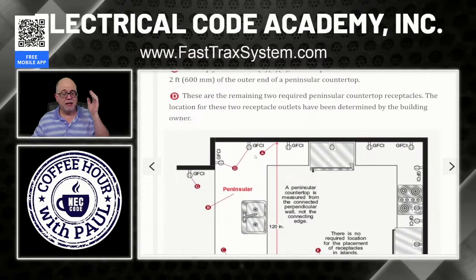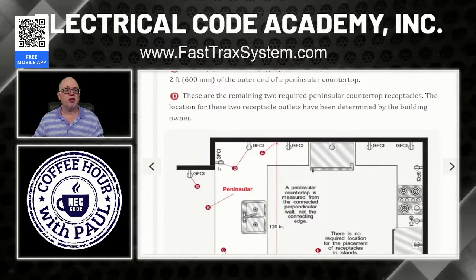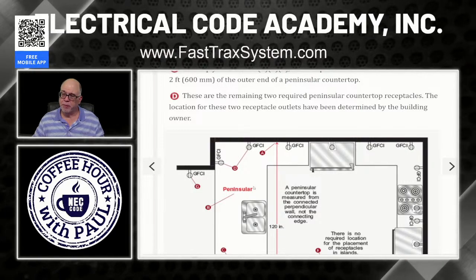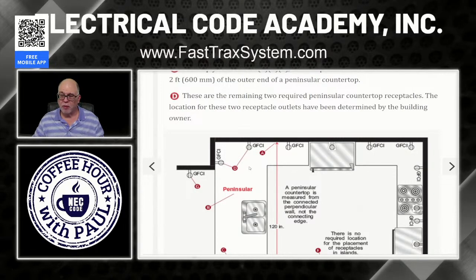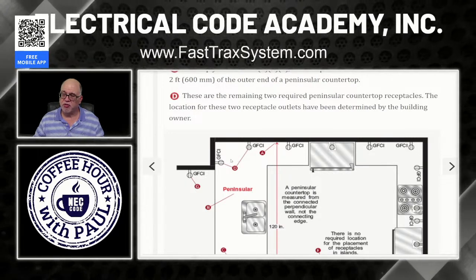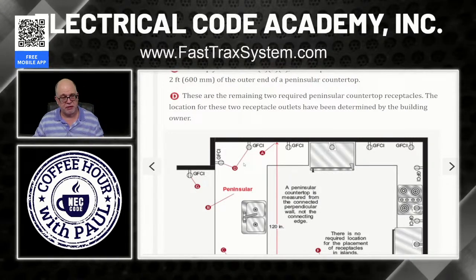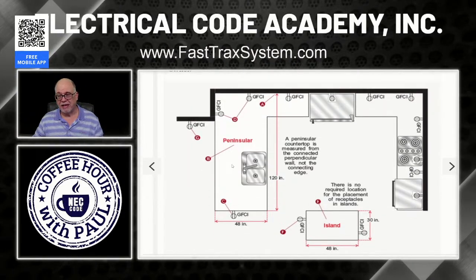Now, incidentally, these receptacles that you see on this wall, they might be here because of the normal wall spacing requirement. Well, they can serve double duty. If they're here and they're in the footprint of this peninsula, then guess what? They can serve also as the other receptacles for this peninsula. They're serving the wall spacing and they're also serving the peninsula, so you've got more than enough receptacles for this peninsula. Make sense? So that's how you apply that.